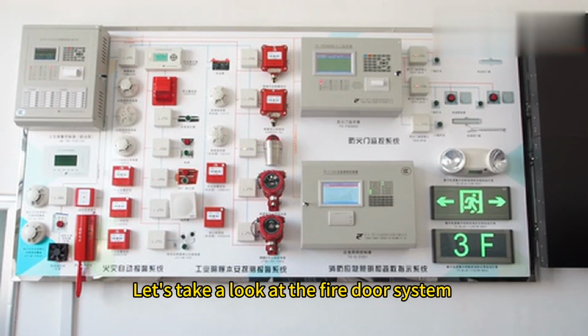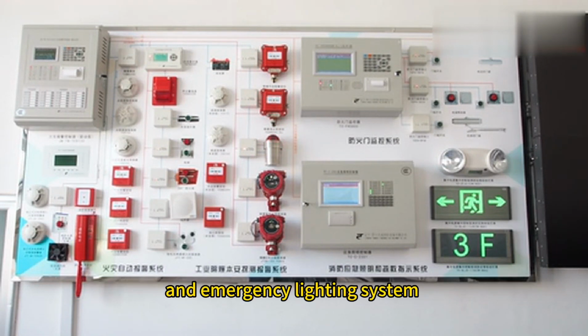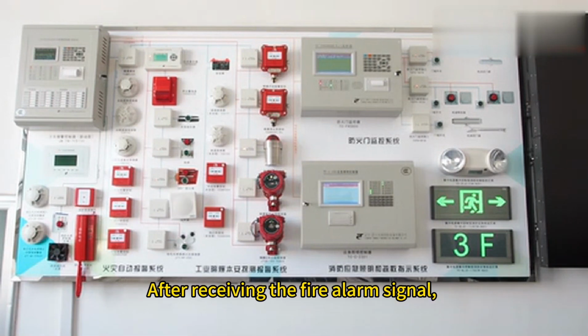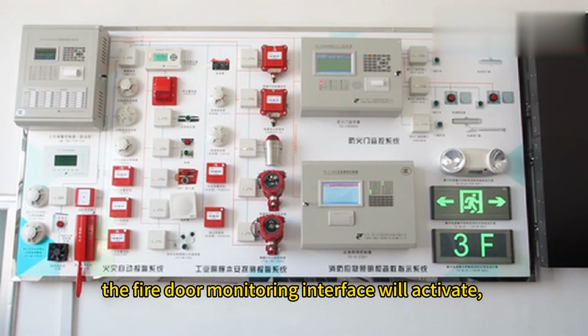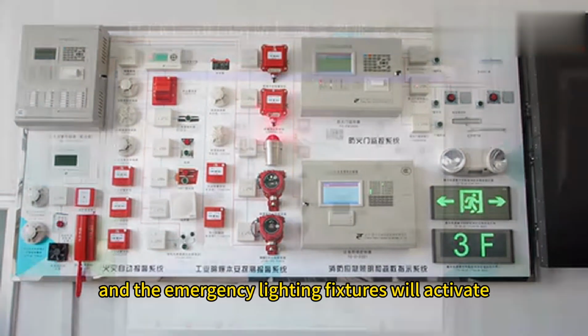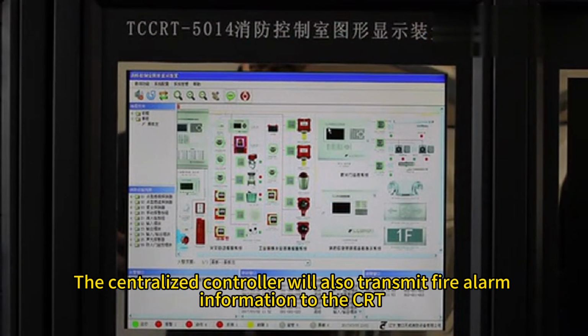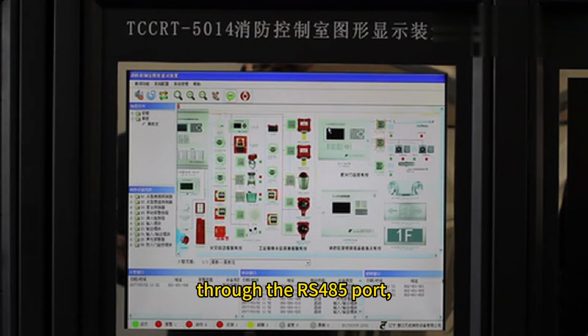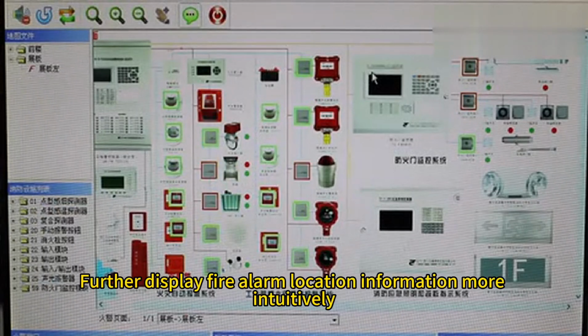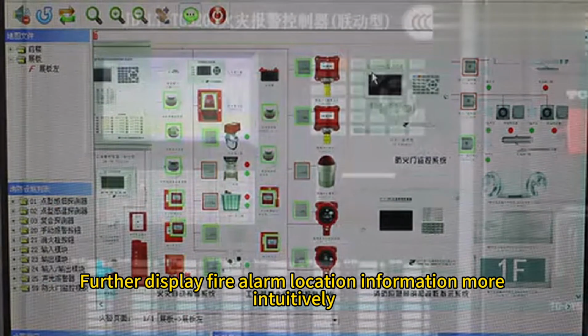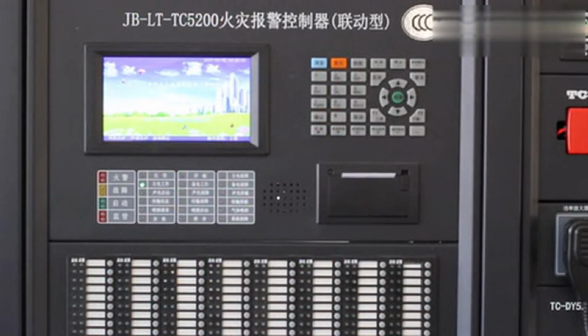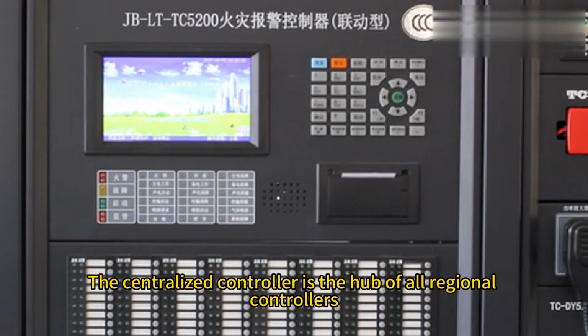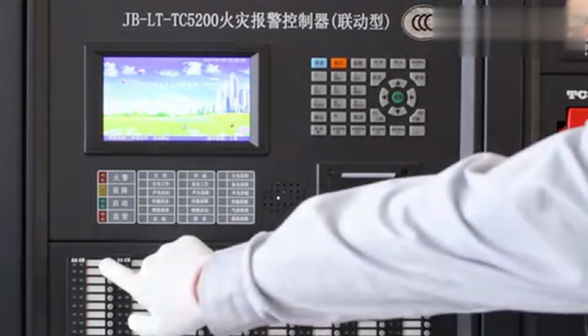Let's take a look at the fire door system and emergency lighting system. After receiving the fire alarm signal, the fire door monitoring interface will activate, and the emergency lighting fixtures will activate. The centralized controller will also transmit fire alarm information to the CRT through the RS485 port, to further display fire alarm location information more intuitively. In the integrated fire protection system, the centralized controller is the hub of all regional controllers.